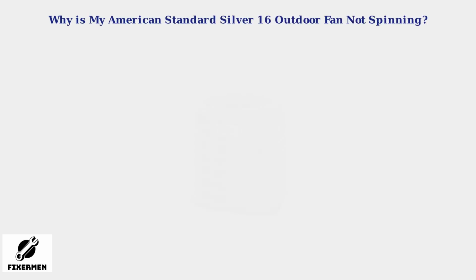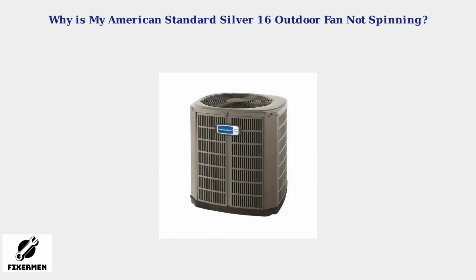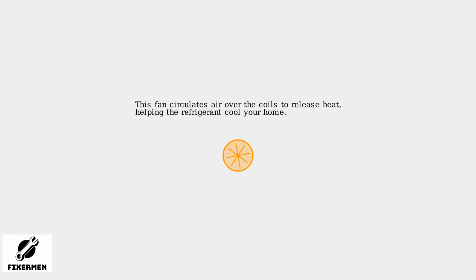The outdoor fan in your American Standard Silver 16 AC unit is crucial for cooling. If it's not spinning, your AC won't cool effectively. This fan circulates air over the coils to release heat, helping the refrigerant cool your home. Common causes include a faulty capacitor, which is the most frequent issue accounting for 40% of fan problems, a failing fan motor, obstructions or debris, or electrical issues.